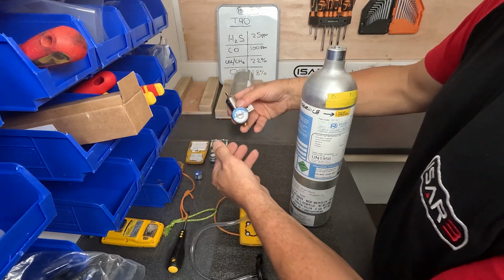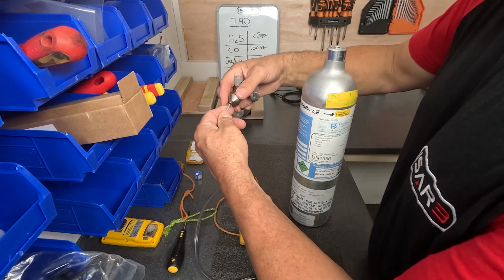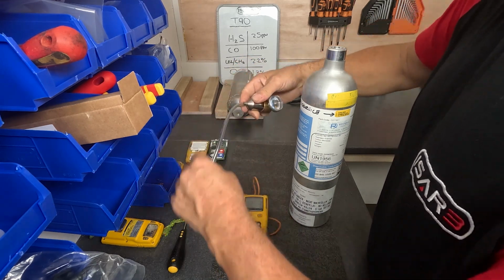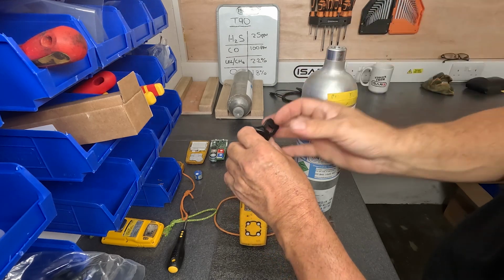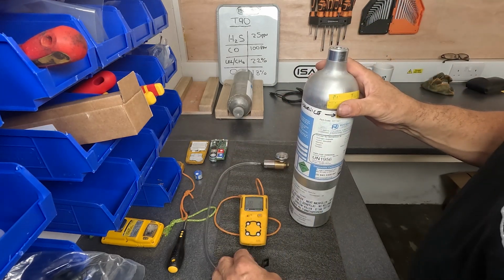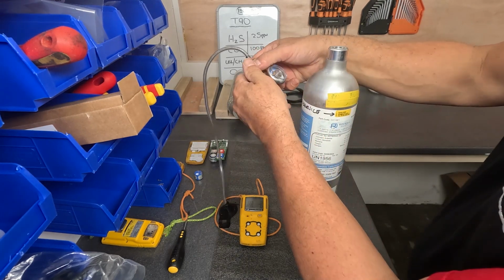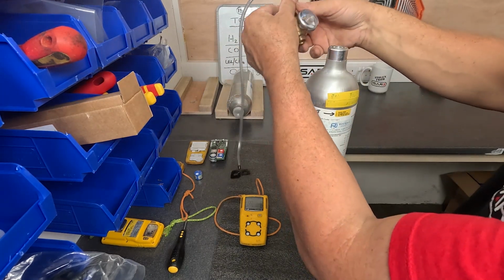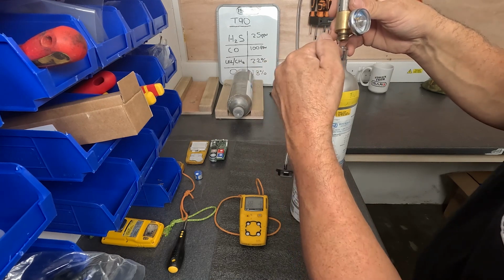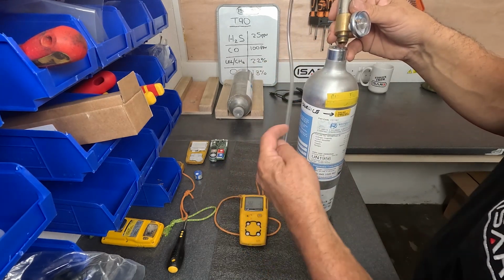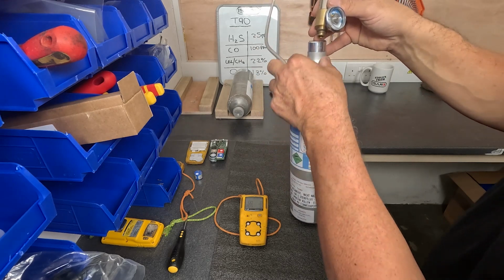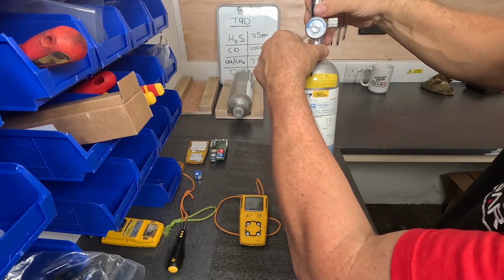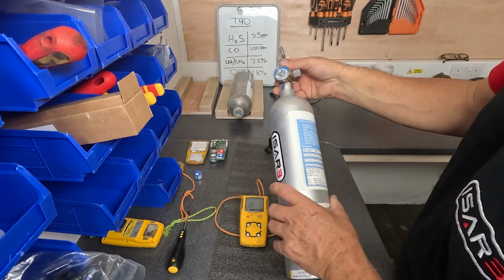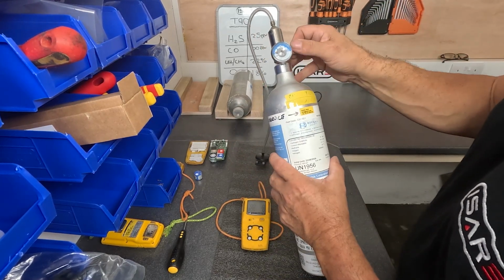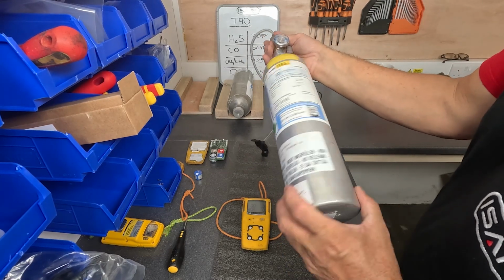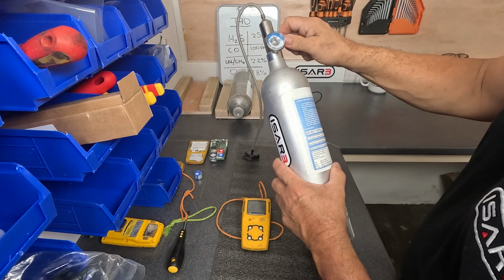What you'll then need is a suitable regulator to go on it, and you'll need suitable hose to connect your regulator to the shroud that will have come with your gas detector when you got it. To assemble this system, what's important is that you open the regulator so that you don't accidentally push and burp some air into here, because the air's got water vapor in it, and water vapor will bind with the H2S that's in there and upset the readings. It's a very fine thread, so take a bit of care to get the thread started correctly. Check your valves open and then just screw the regulator on. As soon as it's on, you can shut off the valve.